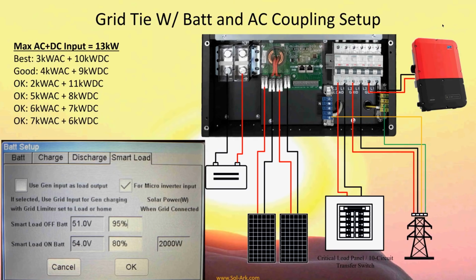What charge controller technology are you using? We use a string inverter, so we support up to 4 strings. They're 500 volts MPPTs for our string inverters built in. This string inverter is just for AC coupling.